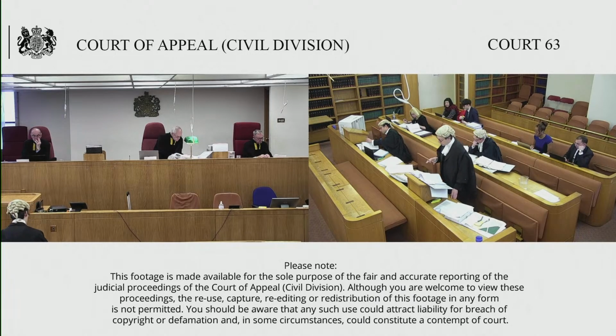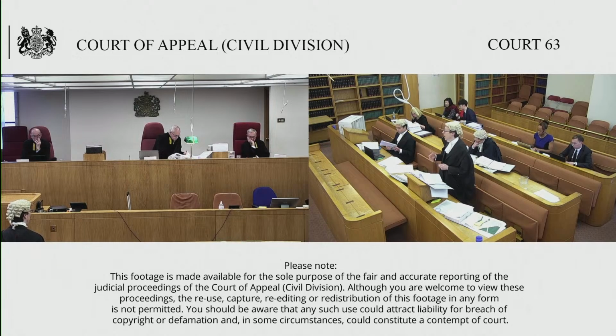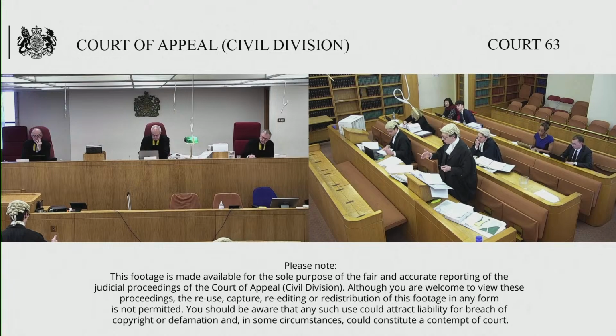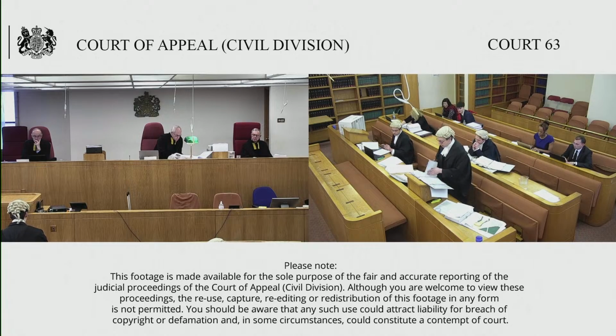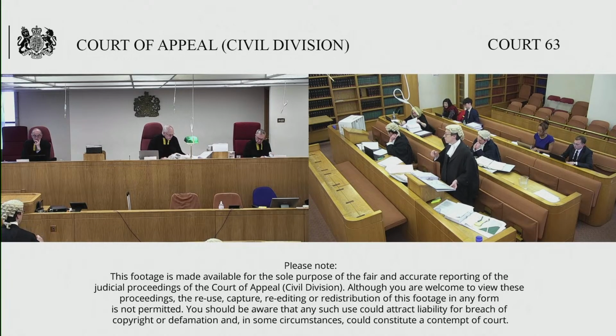In order to export electricity to the grid, one has to increase the voltage so that it matches that of the grid. As I understand it, that's done in two steps: it's increased from the solar panels to a 33 kilovolt transformer, and that's then increased to 132 kilovolts by another transformer, and that's then exported to the grid. So there are two transformers, each boosting the voltage by a certain amount. It was only at this stage, with this application, that the full details of both elements were known. 3.7 does refer to both the 132 and the 33. Yes.